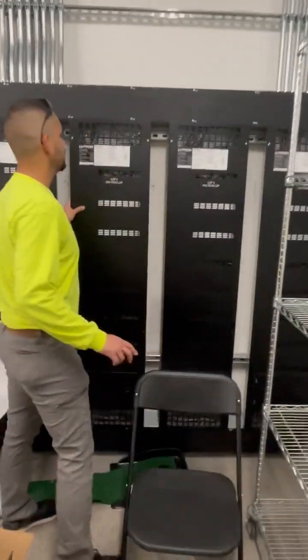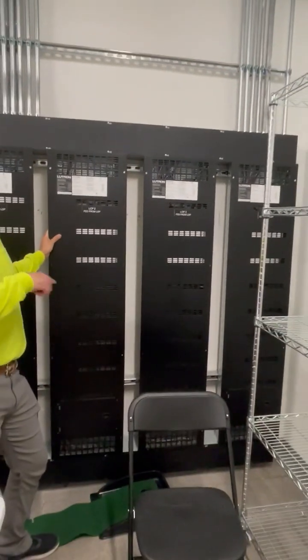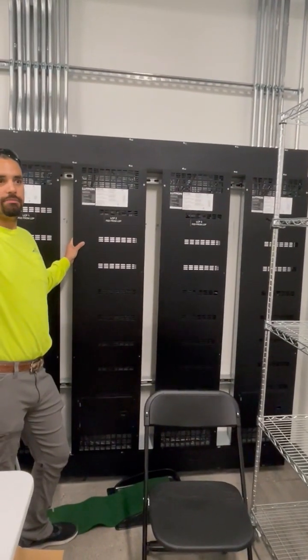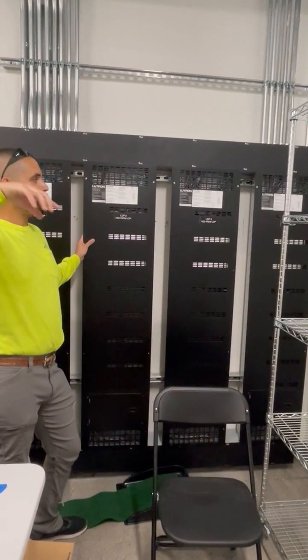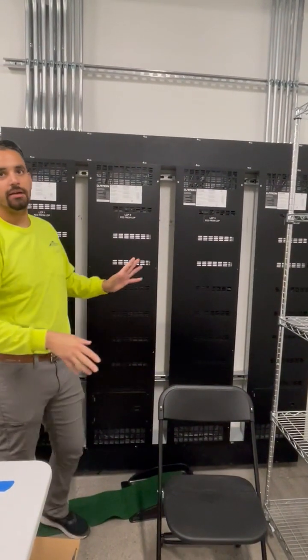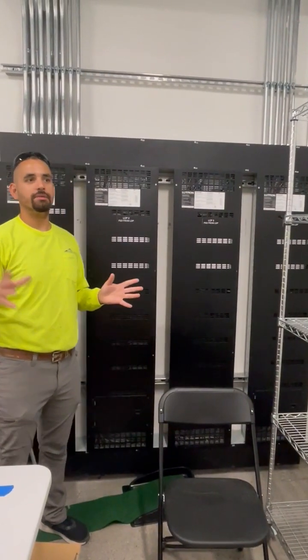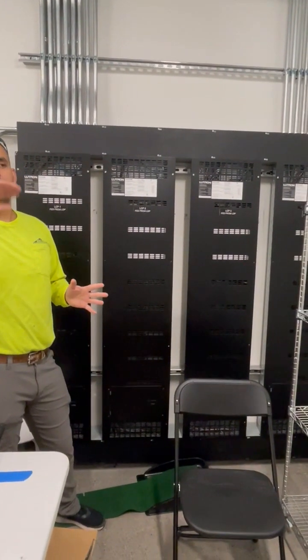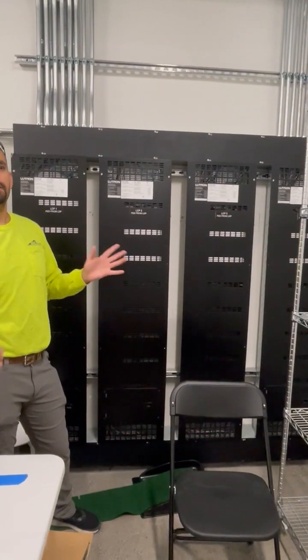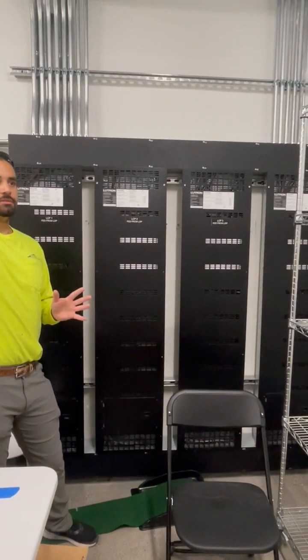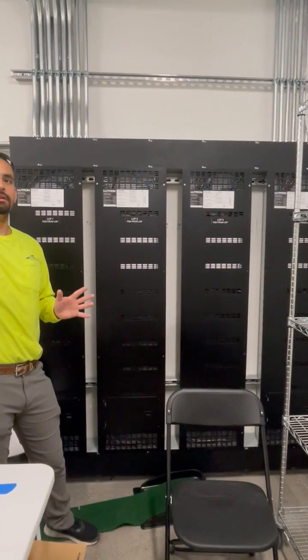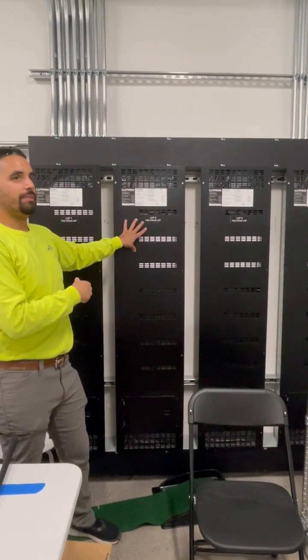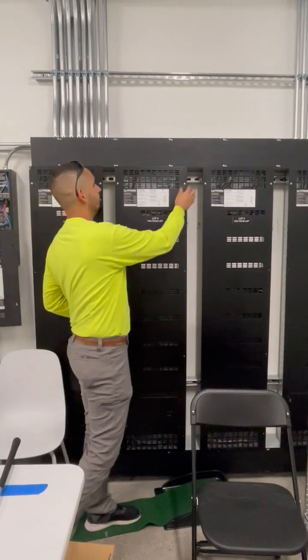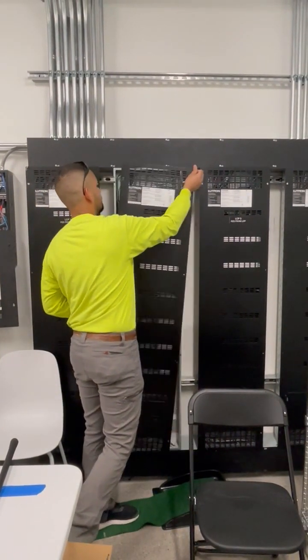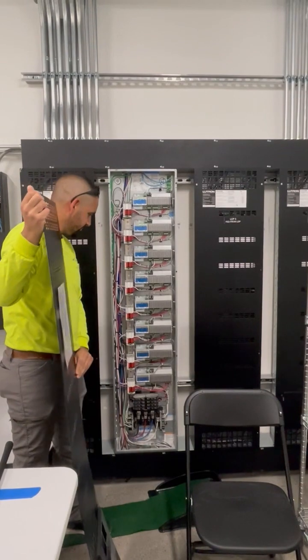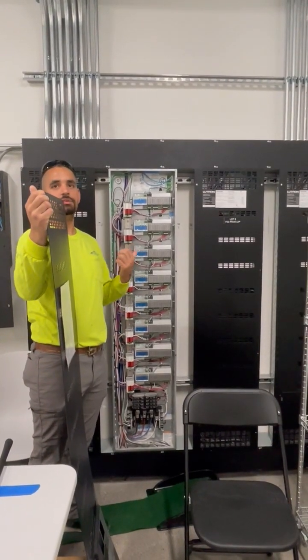Lighting control panel. All this is controlled by the Lutron keypad that's in the manager's office. So this controls all the lighting. A lot of the issues, most of the time, are software issues with Lutron. So if the light's not turning on, the first point would be to check the Lutron system, make sure the system says it's on. I wouldn't really recommend getting in here, because getting in here you will have to deal with a lot of live wires. So if you have to get in here, you'll have to call us.